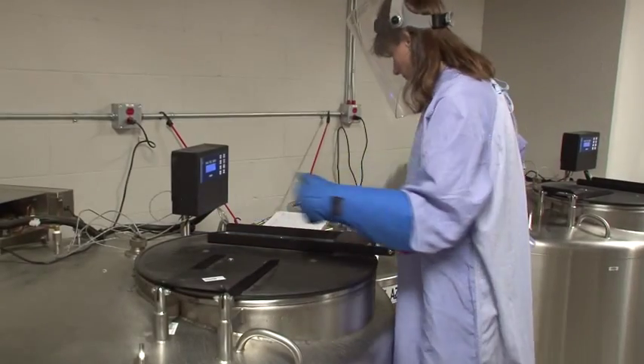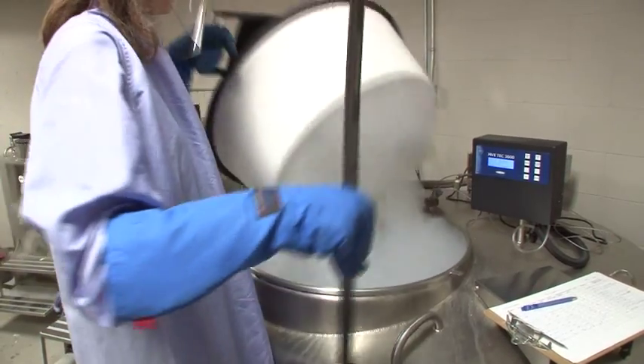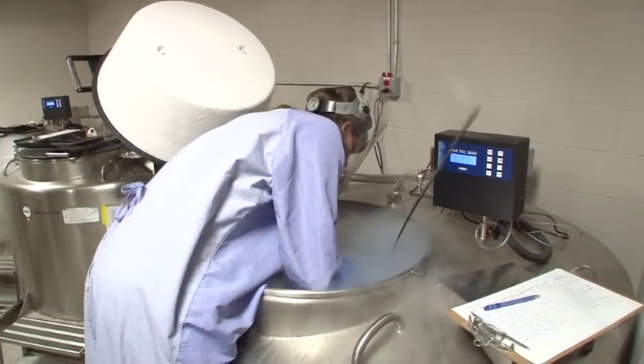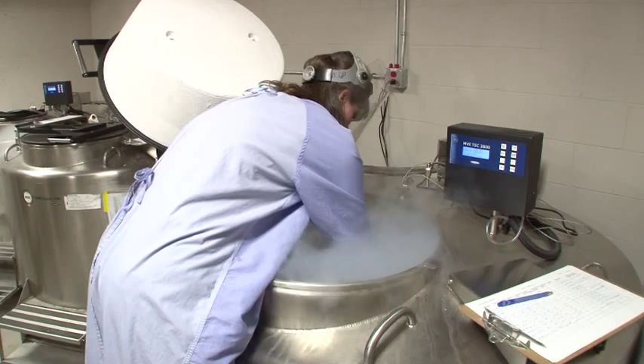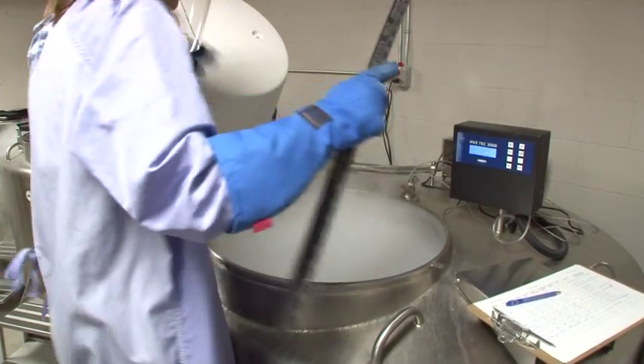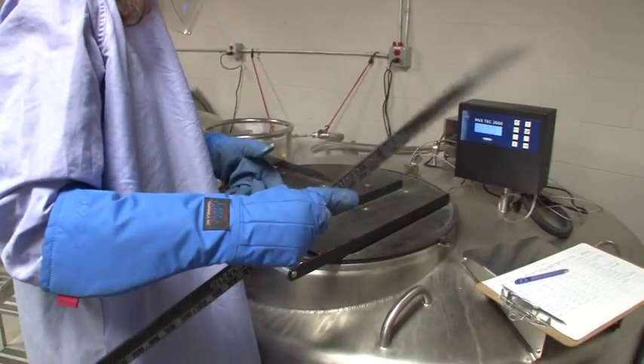We're also storing about 40 percent of our samples at minus 190 degrees Celsius using liquid nitrogen freezers. All biological activity stops at this temperature, so we're essentially freezing the samples in time. We're currently operating three liquid nitrogen freezers, each one holding more than 55,000 samples.